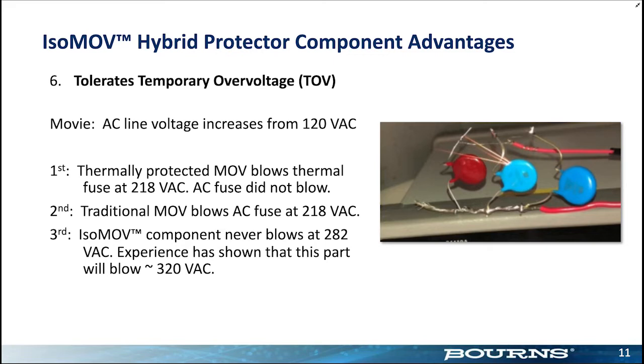And I already show you what you're gonna see here. First, the thermally protected one. It does not blow the fuse because it has that thermal fuse built into it, which does blow. It protects the MOV, which is what it's supposed to do. The second one blows the fuse, and it blows up. The third one never did blow. We cranked that variac as high as we could, and it never did blow. So it's just sitting there, very nice, protecting. Our experience shows that it will blow around 320 volts AC. So let's take a look at that movie.